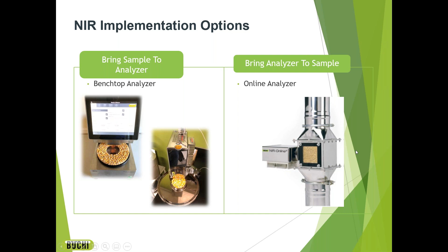Scenario 1: a benchtop analyzer installed in a QC lab. Let's talk about advantages and disadvantages. The advantages are easy installation, for one — it's just another part of your lab equipment. Access to primary techniques for calibration is another asset, along with already having an approval and reporting system within the QC department.